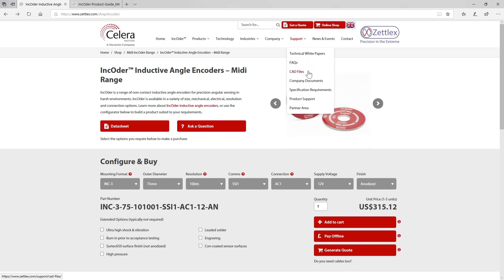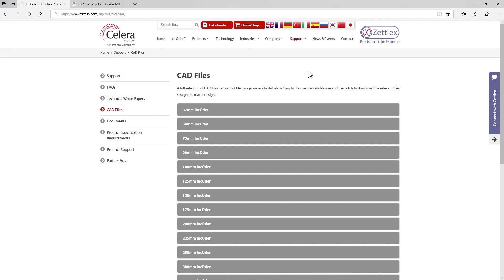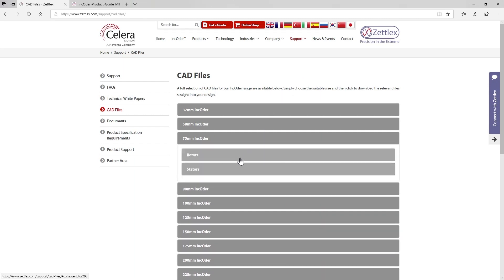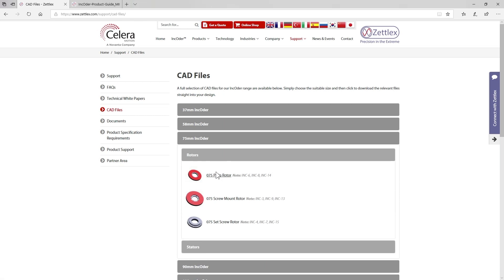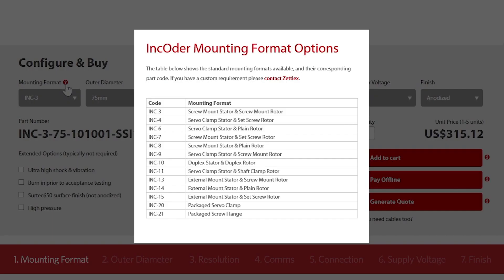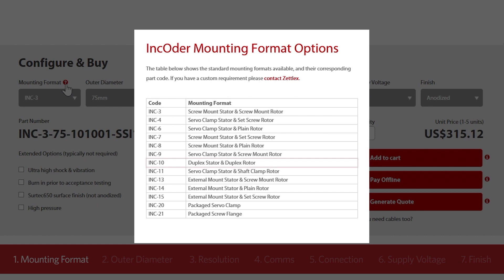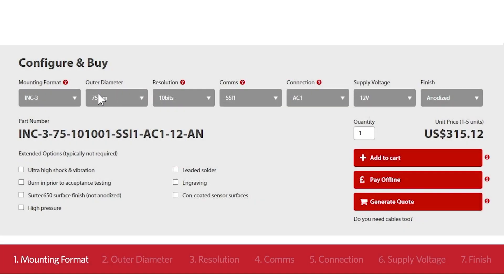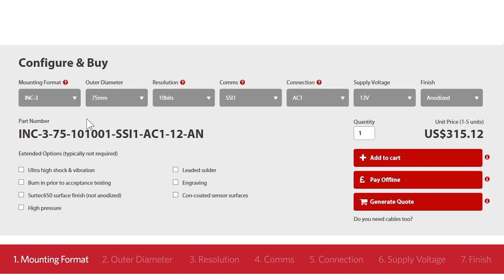It's worth remembering that you can mix and match different mechanical formats of stator and rotor but not sizes, and this can be reflected in the part number. For example, you can have a screw mount stator with a set screw rotor and this will be referred to as an INC 7. INC 10 refers to a duplex arrangement or two encoders in a single housing. These are mostly used for safety related applications where there's a need for electrical redundancy. In our example, we'll pick the most common choice which is INC 3 or screw mount stator and screw mount rotor.